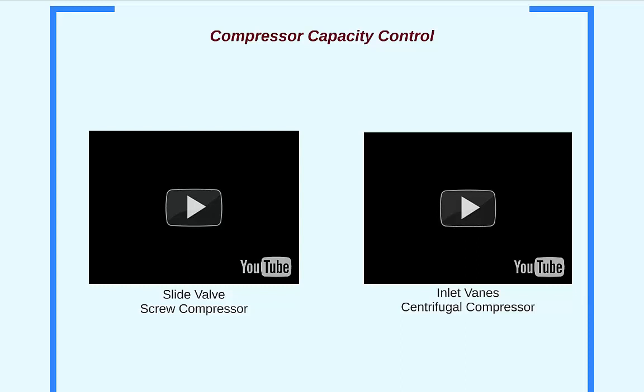Centrifugal compressors use inlet guide vanes to modulate capacity. These movable vanes adjust the direction of vapor entering the compressor. This changes the angular momentum and therefore the centrifugal forces applied to the gas. This next video shows an air compressor with inlet guide vanes and discharge diffuser vanes. Refrigeration compressors don't have the discharge turning vanes shown in the second half of the video. The first 40 seconds are all that apply to this lesson.